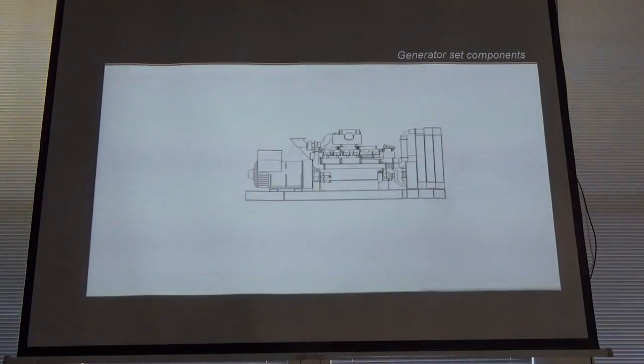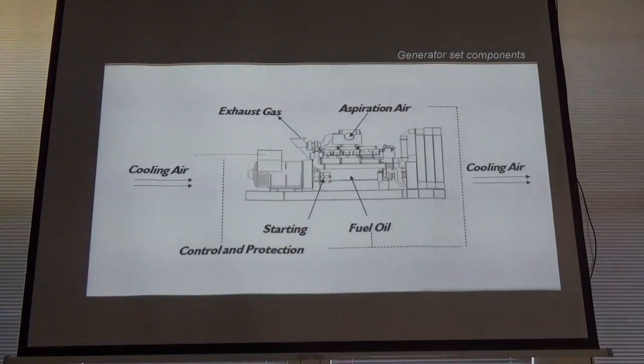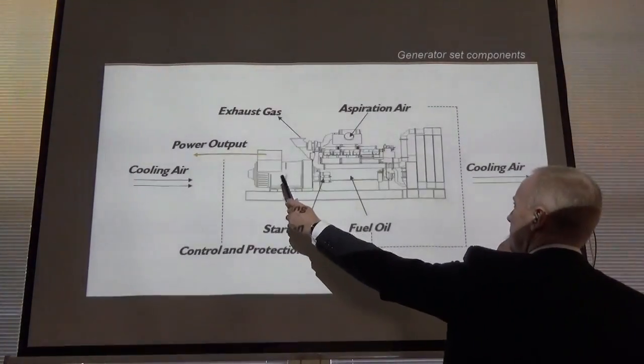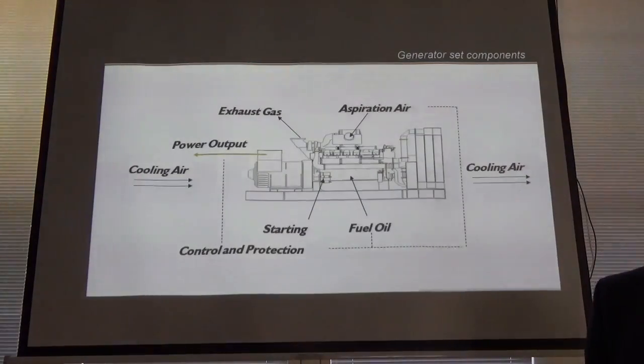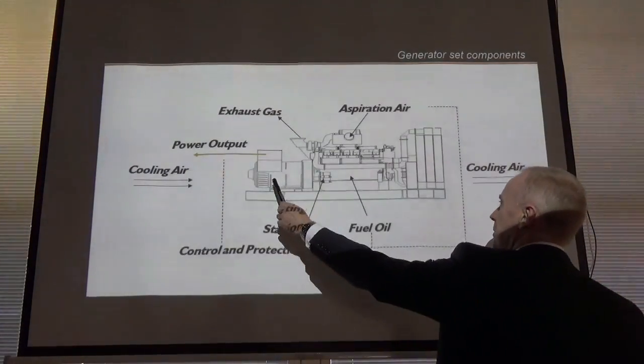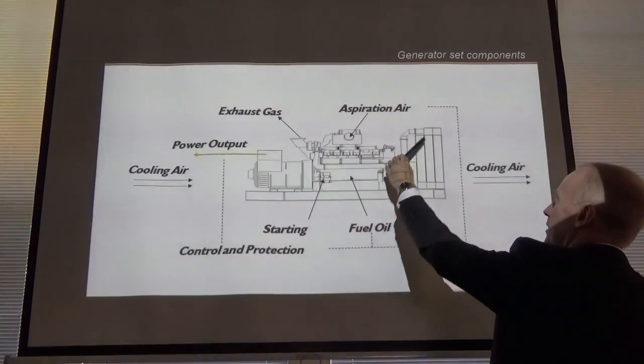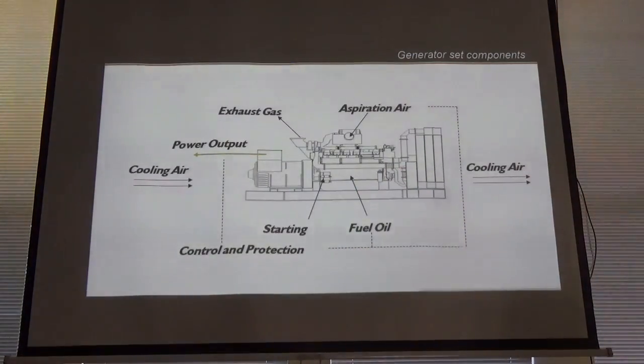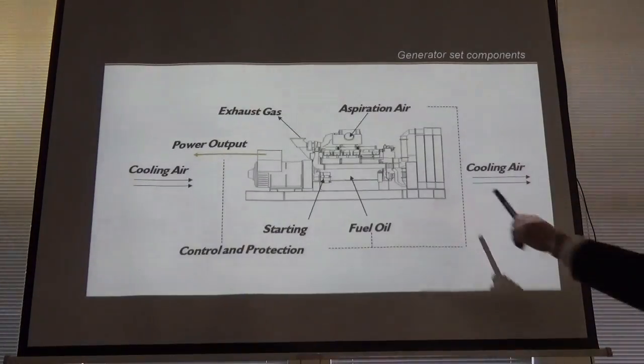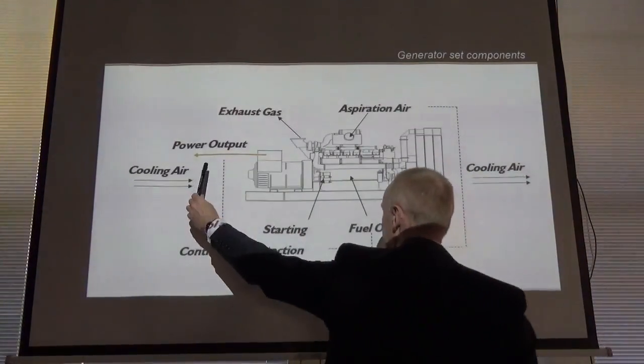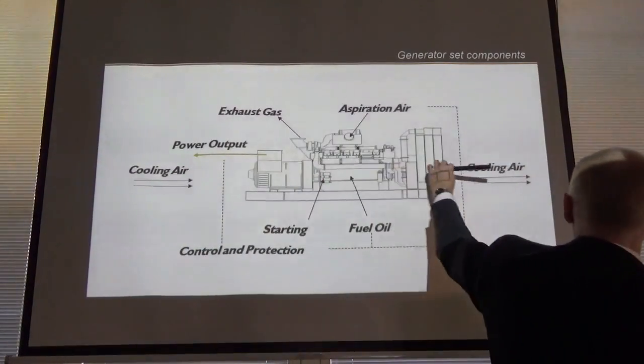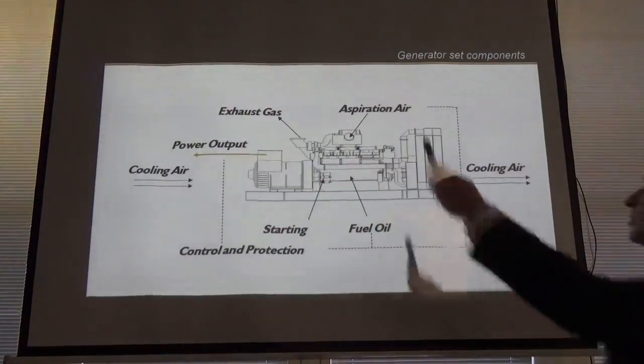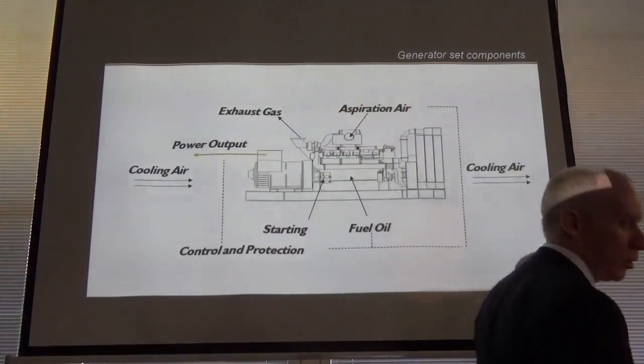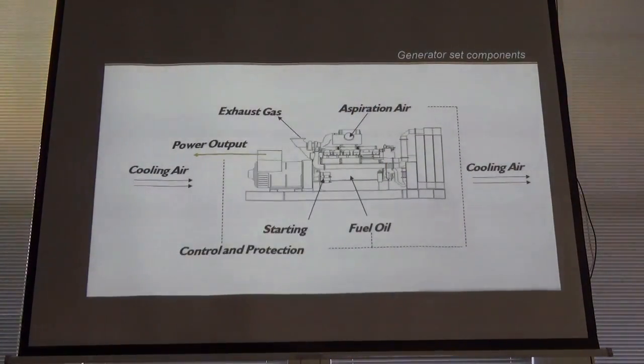Genset itself, let's just go through here. Alternator, typically that will be 95% efficiency and higher. Alternator, then your engine block, and then your fan and your cooling matrix. It's a push-pull fan arrangement here. The key is delivering the inlet air so that it goes across the unit in this fashion. If you're delivering the air into the plant room above, it'll shortcut directly onto the cooler matrix and cause hot spots. So the issue is handling the air suitably to deliver it at the back end of the unit.